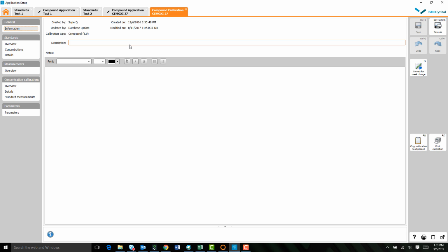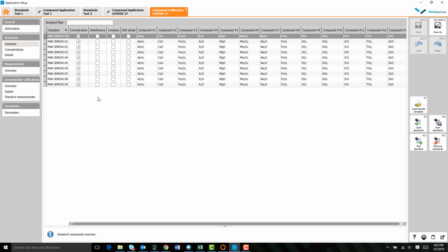So general, again, information, go ahead and populate this, put information in the description for your colleagues, and then put in there what you did and why you're doing it, so people know what's going on with this calibration line, if you had any issues, etc., etc.